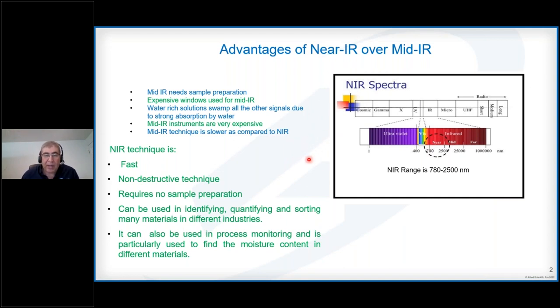Before we get into the DLP spectrophotometers, I want to talk about a comparison between near IR and mid IR. You can see the near IR region here in the 780 to 2500 nanometer range. When you work in the mid-infrared, there are certain limitations. For example, the equipment is expensive, the samples need to be prepared beforehand, water absorption swamps a lot of signals so watery samples are hard to measure, and it's a slow process.